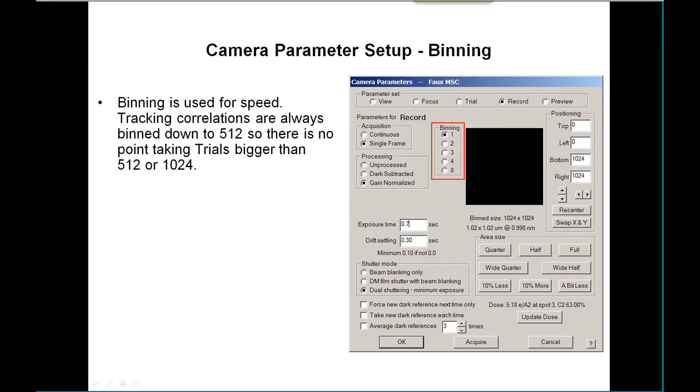Camera parameters setup - you'll go into this dialogue a lot. Binning is a very important thing with CCD cameras. We use it for speed, basically, because the CCD can bin before it has to read the data out, and this makes it all come out much faster.